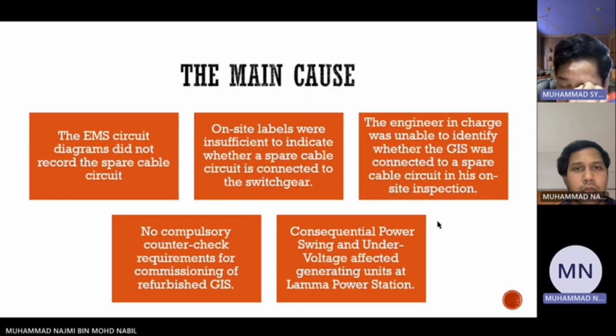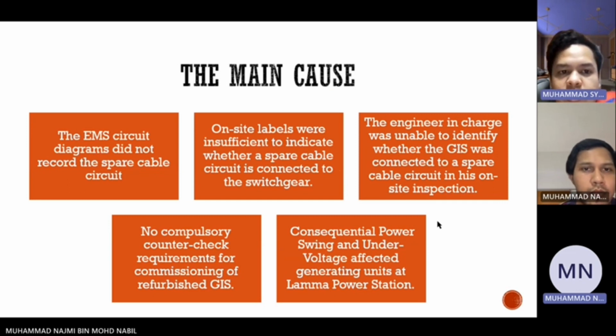Okay, next, this is the main cause of the incident. First of all, the EMS circuit diagram did not record the spare cable circuit. After that, on-site labels were insufficient to indicate whether a spare cable circuit is connected to the switchgear. And number three, the engineer in charge was unable to identify whether the GIS was connected to a spare cable circuit in his on-site inspection. And number four, no compulsory counter-check requirements for commissioning of refurbished GIS. And lastly, consequential power swing and under voltage affected generating units at Lamma Power Station.